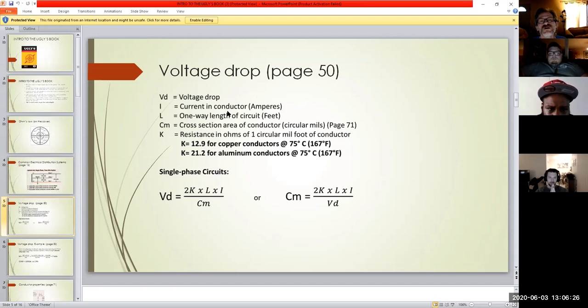They ask how much current do we have in the conductor, in the wire. The L is for length, how many feet are we running—if it's 500 feet, throw that in there. The CM is circular mils, which measures how thick the wiring is. So if you're using a number 14 or number 12 AWG, you'll find it's measured in circular mils.